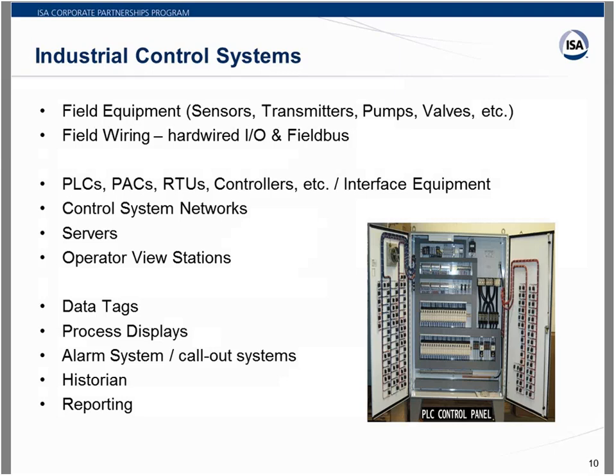In a typical industrial control system, there are a number of components. You have the field equipment - your analyzers, instrumentation, valves, pumps, control surfaces, and any measurement instrumentation. You have the wiring that brings that into the control system, and the controllers, whether it's a PLC, an RTU, an RTAC unit, or whatever the vendor calls it - the box that all the instrumentation hooks into, which also runs a control program for automatic control. You have a control system network, various servers depending on architecture, and operator view stations. These systems work using data tags containing your measurements or control variables, moved back and forth to control your process. You'll have an alarm system for calling out alarms to a control room or roving operator, a historian for trending and data analysis, and a reporting component.